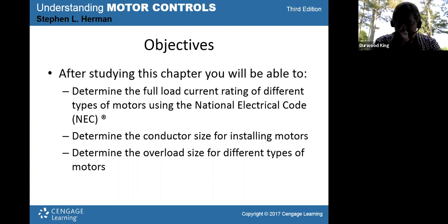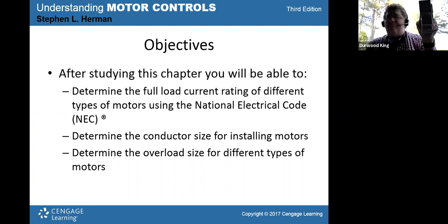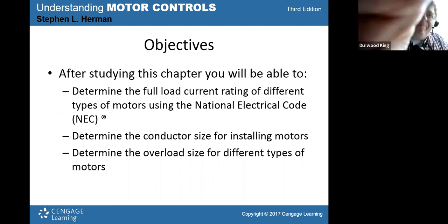So, okay. We're going to look at how you look up the full load current rating of different motors. How do you determine the wire size, or the conductor size, for a motor? And how do you determine the overload size? Like if you see my webcam, the overload relay up under the contactor, how do you actually know what to set that to? That's something we're going to be looking at.